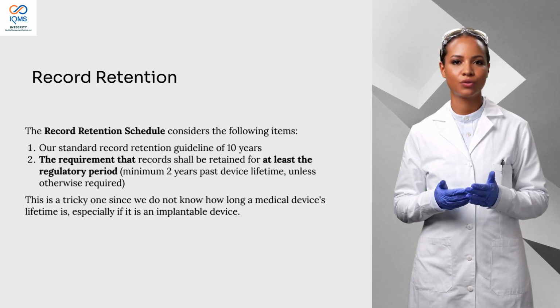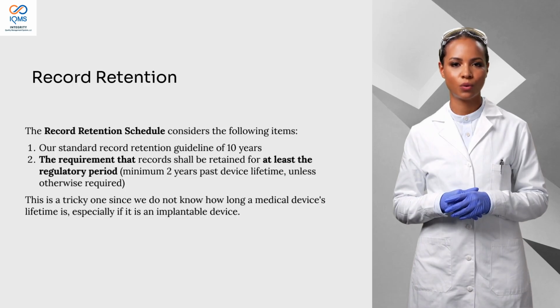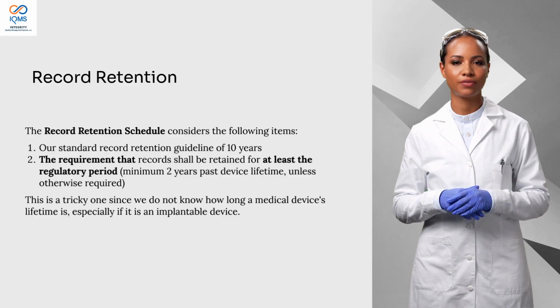Our standard record retention guideline of 10 years. 2. The requirement that records shall be retained for at least the regulatory period, minimum 2 years past device lifetime, unless otherwise required. This is a tricky one since we do not know how long a medical device's lifetime is, especially if it is an implantable device.